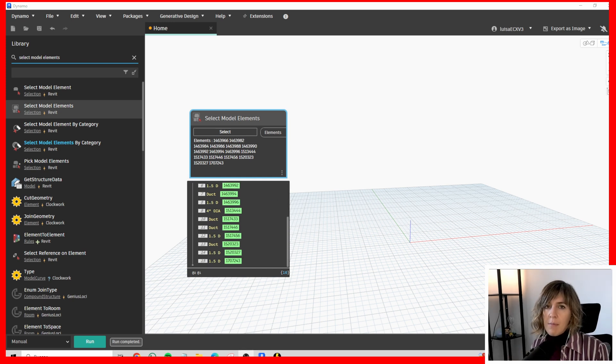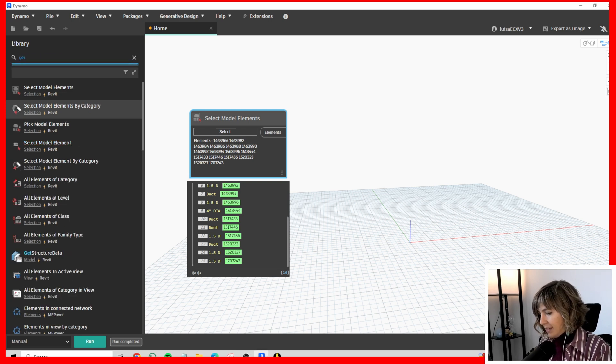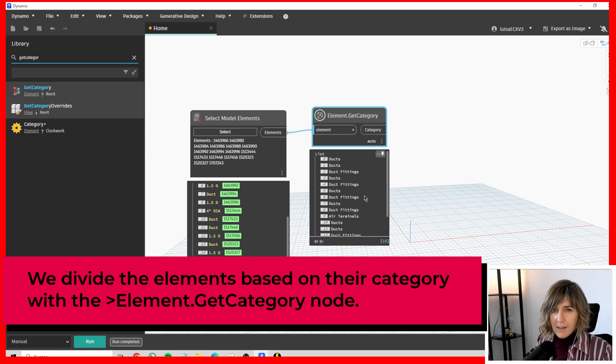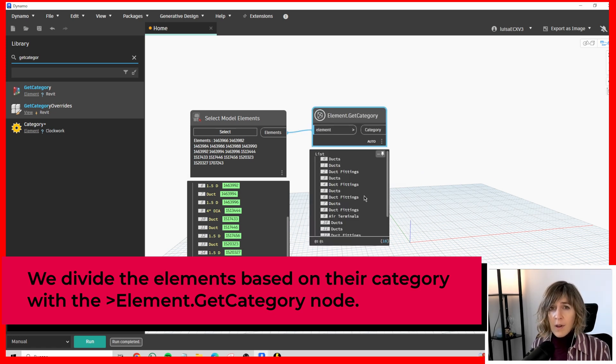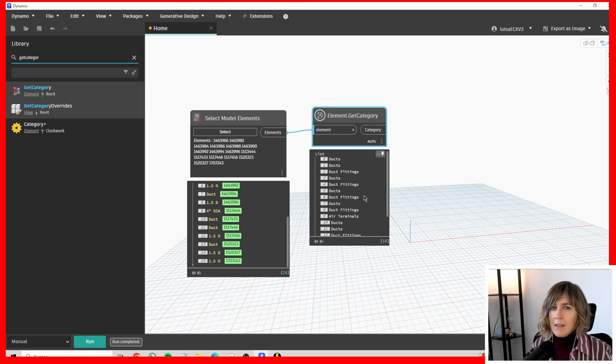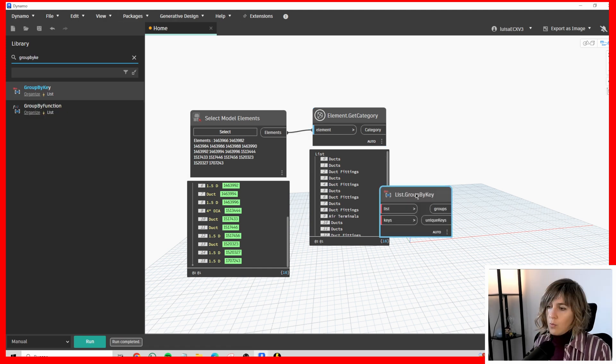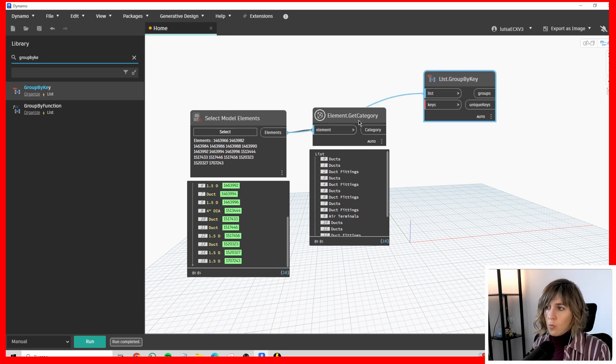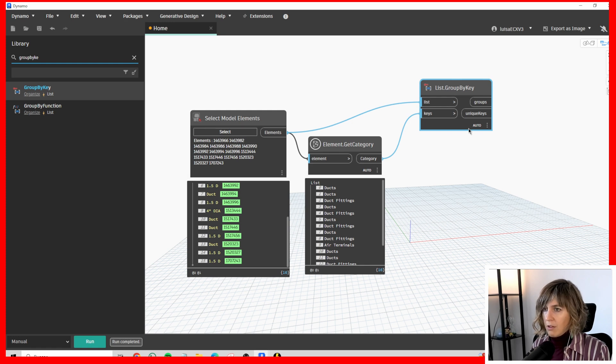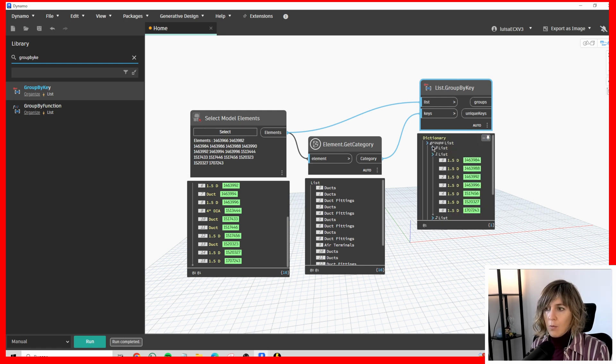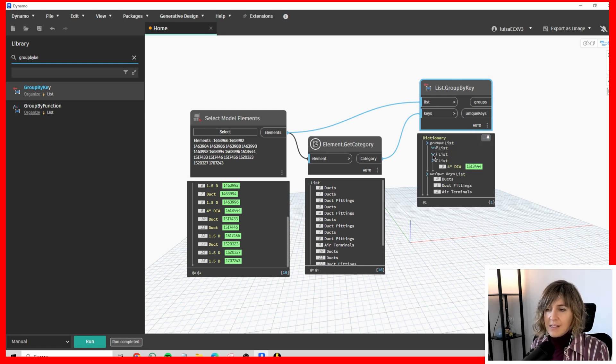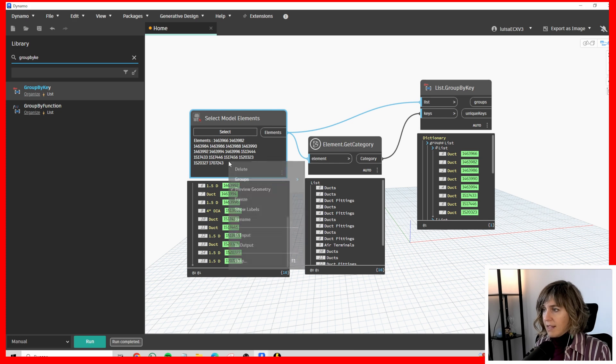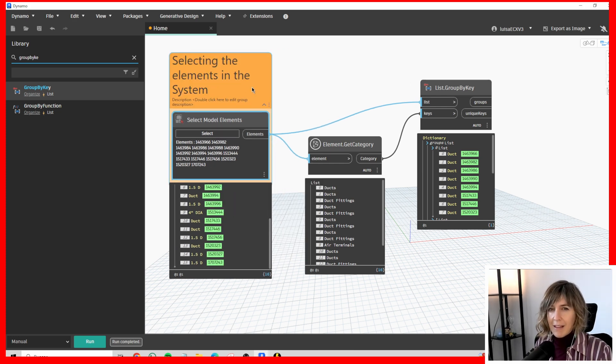Then, I'm going to separate the elements by category. I'm going to get the category of these elements with element get category. There are different ways of getting the length - the ducts do have the length directly, but the other pieces may not be so direct. Now let's group the different elements by their category with a group by key node. Which elements have to be grouped? The ones on the system. What is the key to grouping them? Their category. This way, we have the ducts in one list, and the duct fittings in a second list, and the air terminals also on a third list.